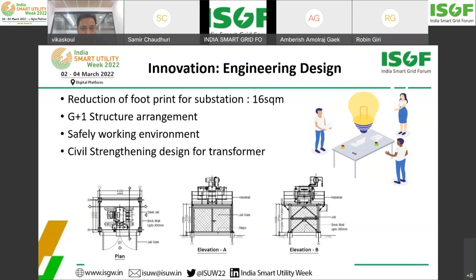Now the difference between the tower mounted and conventional substations is that augmentation is possible in the tower mounted substation. The other solutions I showed you are of fixed rating, and augmentation is very difficult in package substations, micropad, or underground designs - special equipment is required there. In tower mounted, no special equipment is required; we can use existing equipment.